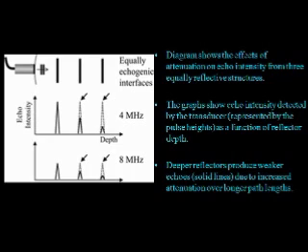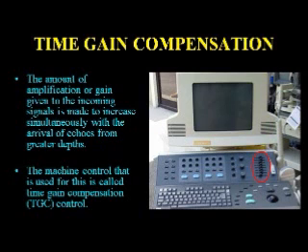As the ultrasound goes deeper, the reflected ultrasound beams give weaker signals due to attenuation. To compensate for this decreasing signal, we amplify the returning ultrasound from deeper structures. This is called time gain compensation.